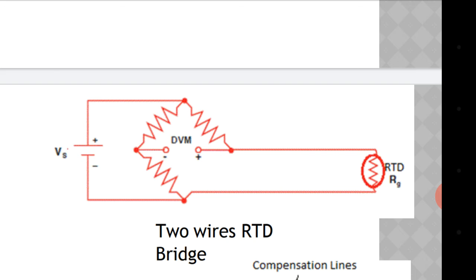The RTD sensing portion is inserted into the liquid whose temperature is to be measured. If temperature increases and we are using PTC (positive temperature coefficient), the resistance of the RTD will also increase. The other three resistors in the circuit are of fixed values so they cannot change, meaning the RTD changes based on temperature, the bridge becomes unbalanced, and we get the potential difference.